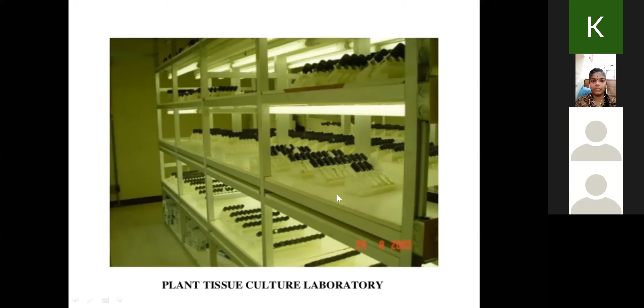Media preparation should not be in the place of inoculation. It should be separate. So you should have a separate room for media preparation, a separate room for sterilization of the media, and a separate room for storing the media. None of these should be inside the inoculation chamber. The inoculation room should be totally separated from media preparation, sterilization, and storage. And you need a separate washing room.